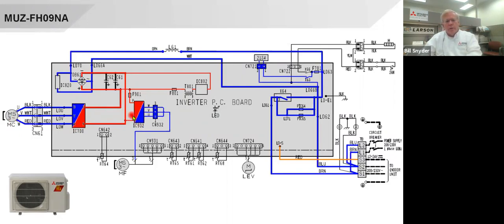we have a circuit here that converts it, and it says U, V, and W, and that is going down to the fan motor on the outdoor unit. So they do it a little different here. We're actually sending three-phase AC directly to this fan motor. And then we've got 5 wires that are your signal wires that would tell that motor what to do and respond and tell it what it's doing.